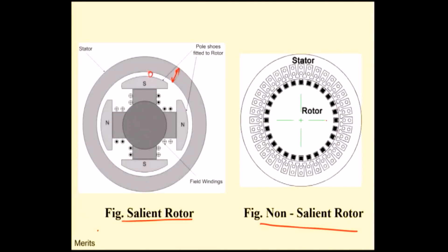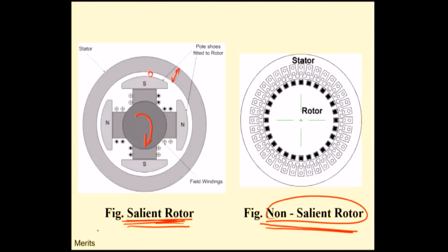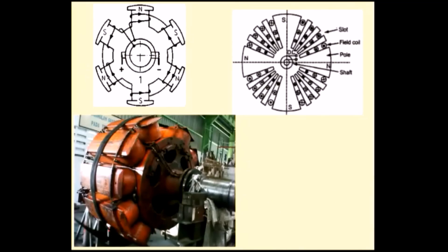In the salient pole rotor, if you rotate at high speed, the projected poles produce more noise because the air gap is small and the rotor has to push through the air. In contrast, the non-salient pole rotor gives noiseless operation. The salient pole rotor has a larger diameter, making the entire machine larger, and it is not a robust construction. The non-salient pole rotor has a smaller diameter and is robust in construction. A practical 10-pole salient pole rotor can be seen as an example.